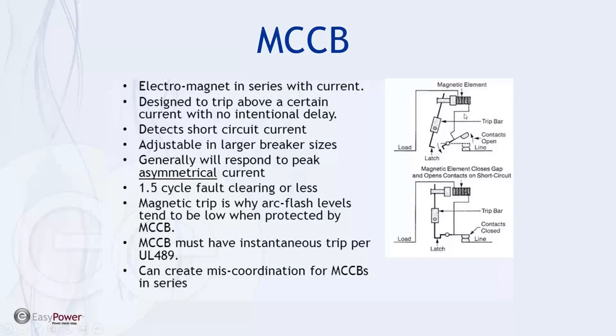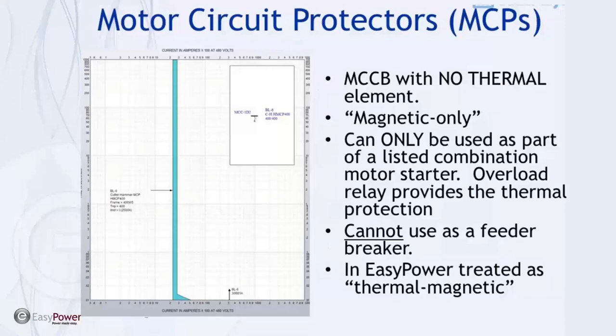The electromagnetic element is a coil in series with the current that at a certain level will actuate and interrupt. These work in conjunction in a molded case circuit breaker. According to UL listing, the molded case circuit breaker must have an instantaneous trip. Because all MCCBs have an instantaneous trip, this causes the potential for miscoordination. A special case is the motor circuit protector — basically there's no thermal element, only magnetic, so we only have an instantaneous trip.